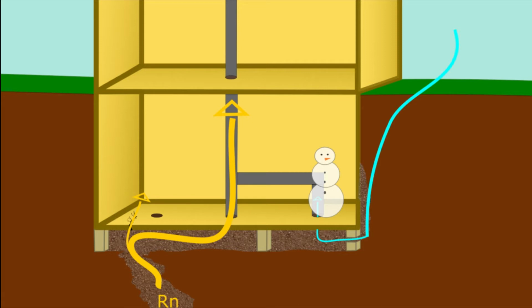In theory, the mitigator depressurized the entire slab and reversed the airflow through the cracks, but this isn't necessarily the case. The actual pressure at the crack was never measured. There might not even be access to the crack if it is at the expansion joint under a finished wall. Another consideration is that the mitigator may have depressurized the whole slab now, but what about 6 months from now when the water table is different?